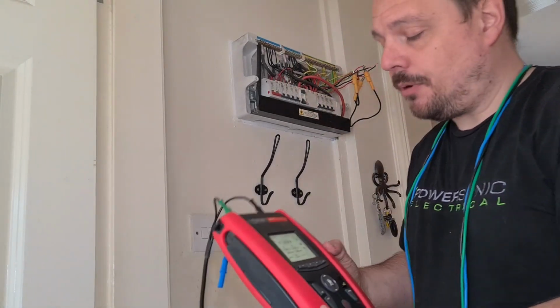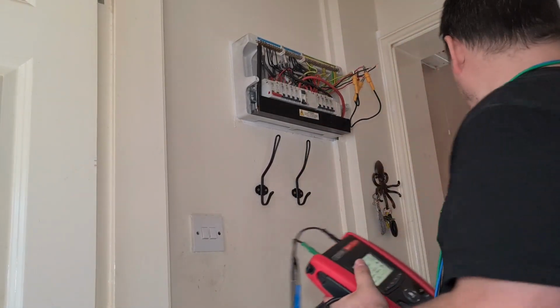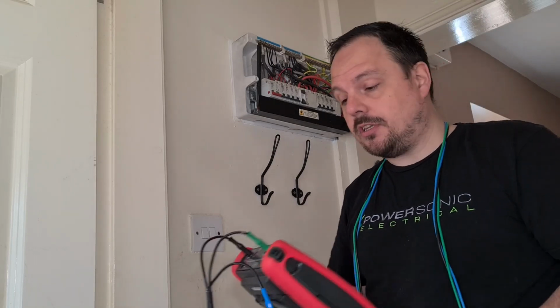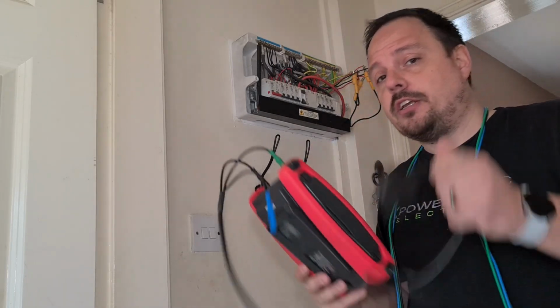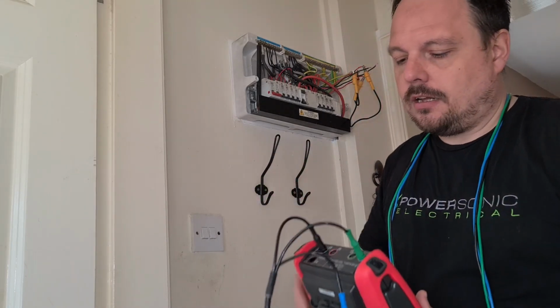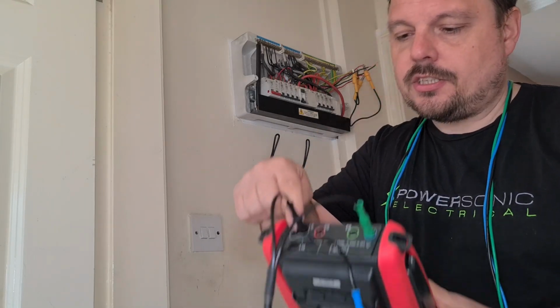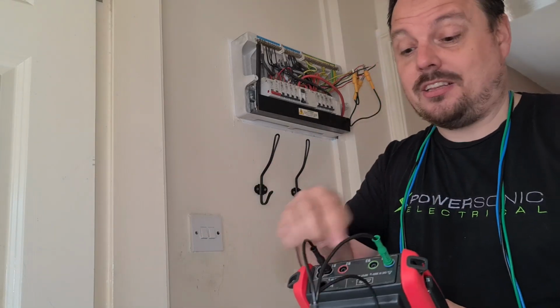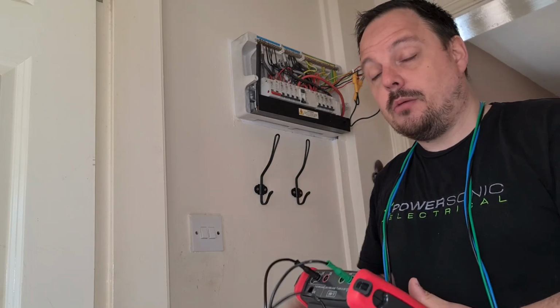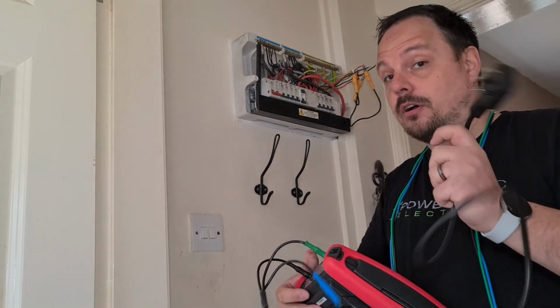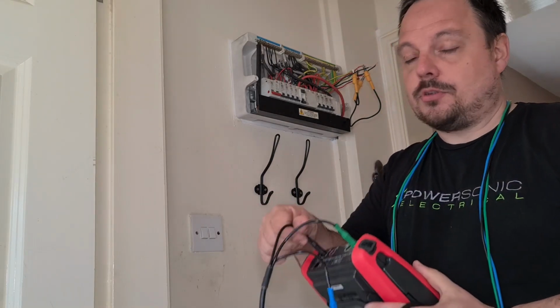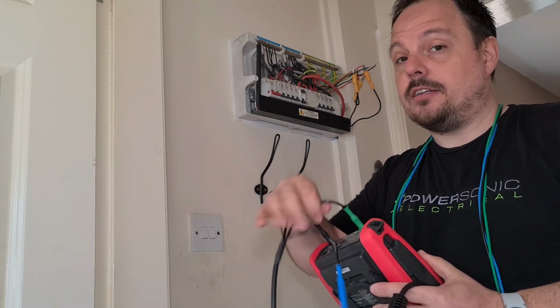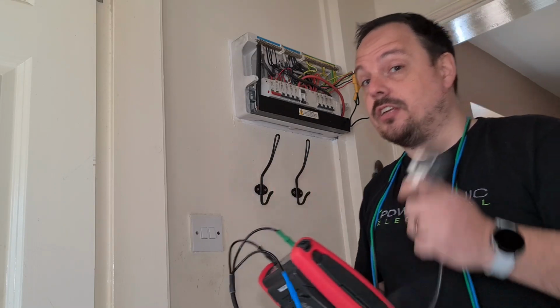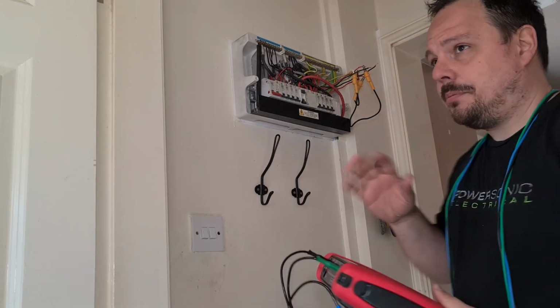Okay, so I've got 0.18. It's actually a very small ring that just goes to this little utility room to the side of me there. Point of note when you're using this lead, on the tester you need to be connected into the B1 and basically the line and neutral terminals, but you need to remember that you're measuring on the socket outlet between line and earth, so you need to put your line and your CPC into those terminals so you can take the reading. And that kind of plays out with the maths.